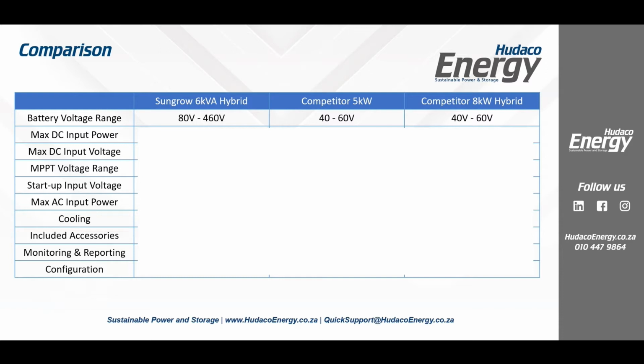throughout this entire system. Okay, so when somebody says it's a 6 kVA hybrid, well, is it really? The 6 kVA, remember, only refers to the circuits that we're going to back up and provide backup power to from batteries during grid failure. Okay, other than that, for the price of a 6 kVA unit, you're actually looking at a 13 kVA system.